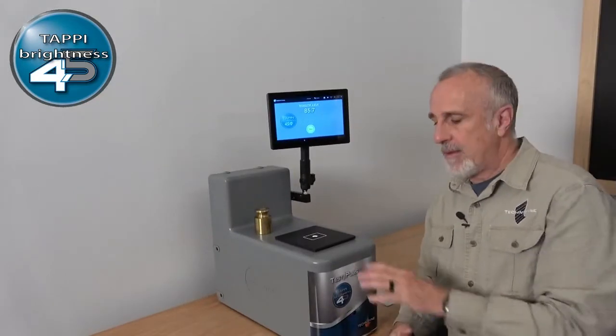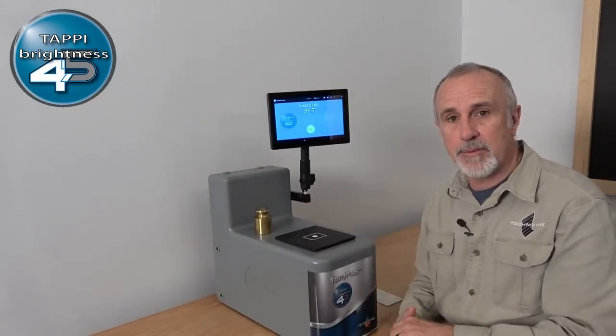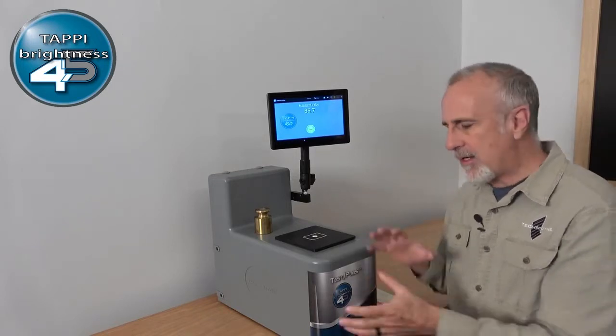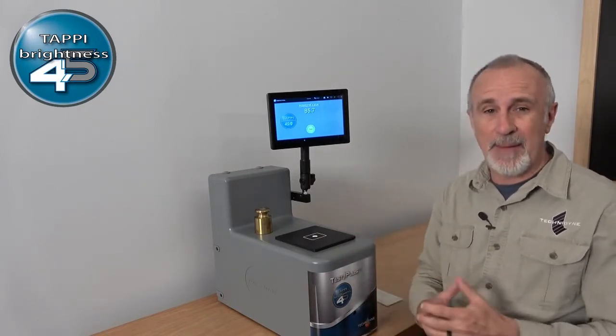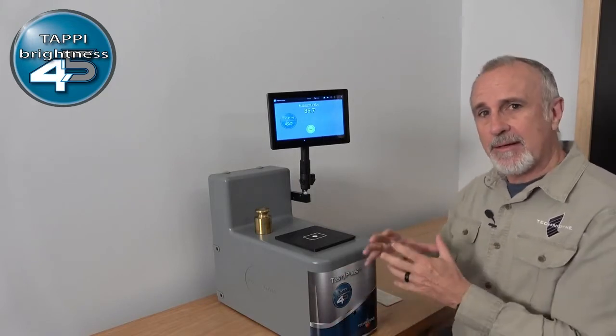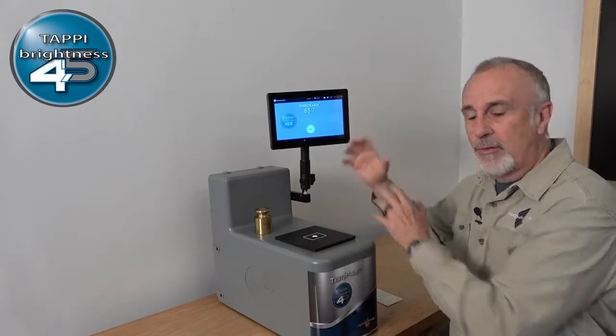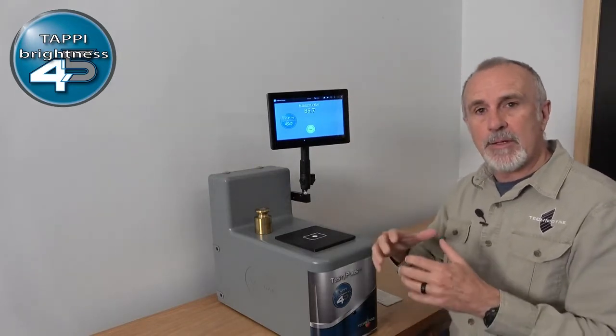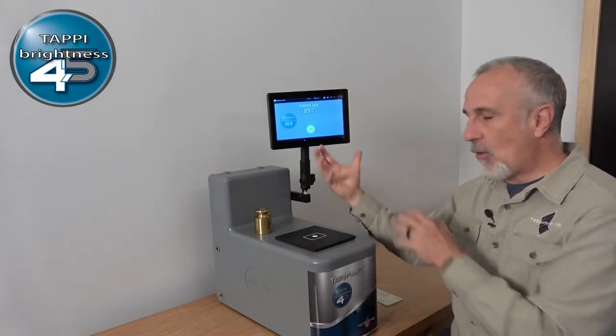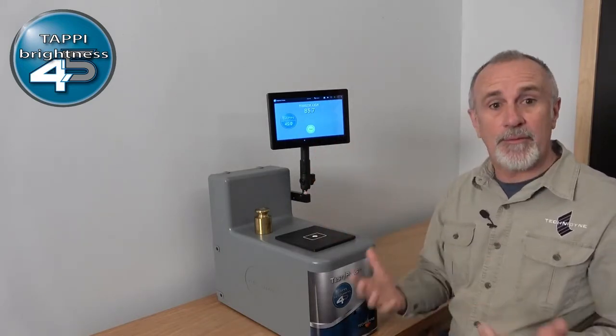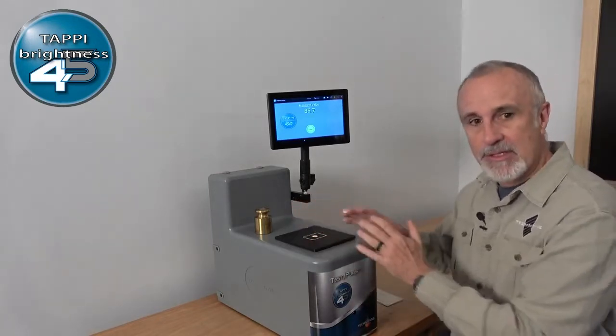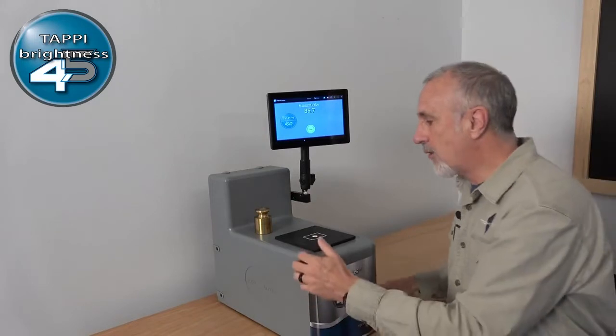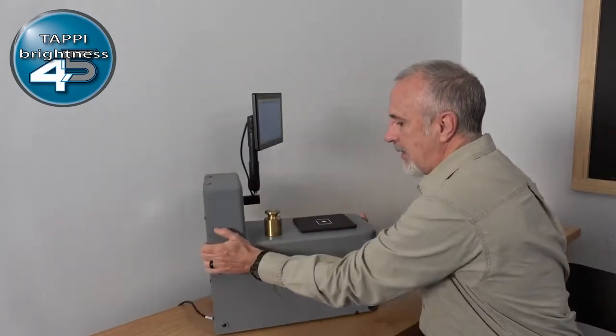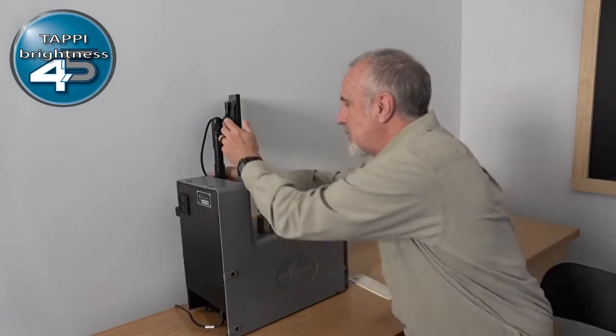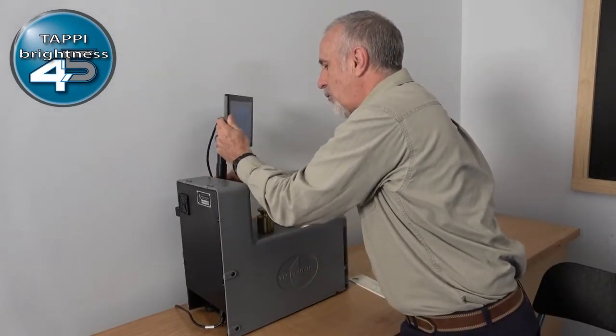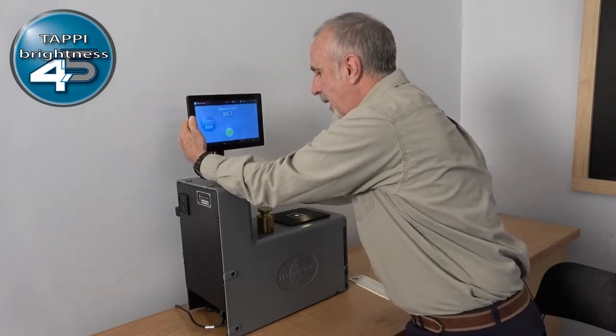Now, when we developed the Test Plus directional TAPPI brightness instrument, we talked to a lot of our different customers, and they said we would like to be able to configure this in different ways depending upon the application and depending upon our testers. So in our design, we put the display external to the instrument, so that your interface can be oriented depending upon how you have this instrument set up. A number of customers already have the Test Plus instrument and they have it sitting in this orientation. There are others, though, that prefer to set it up more like this. The reason they choose this way is because that was consistent with how the S4M, or one of the older S4 instruments, was set up.